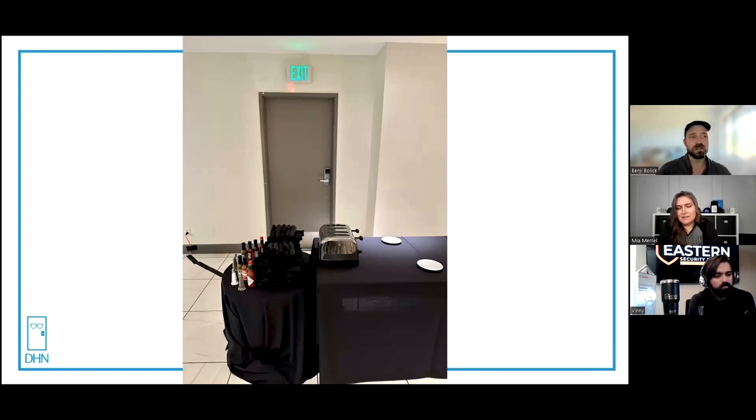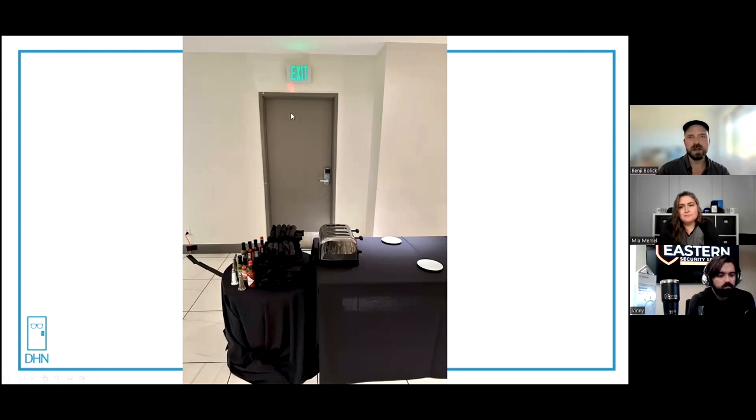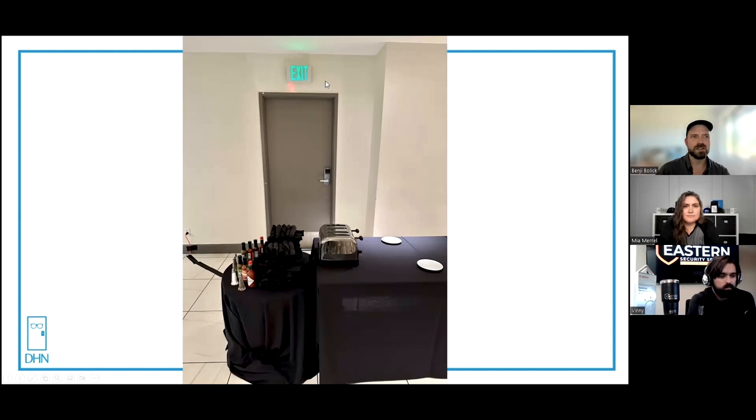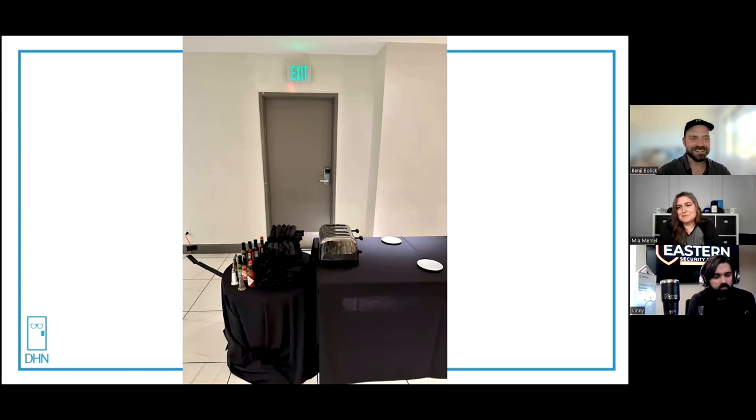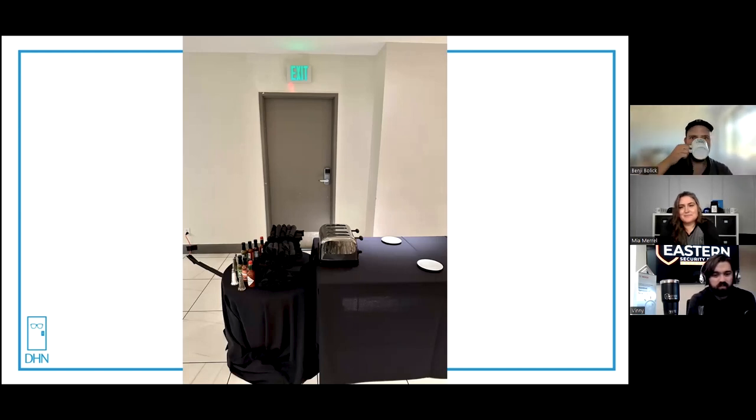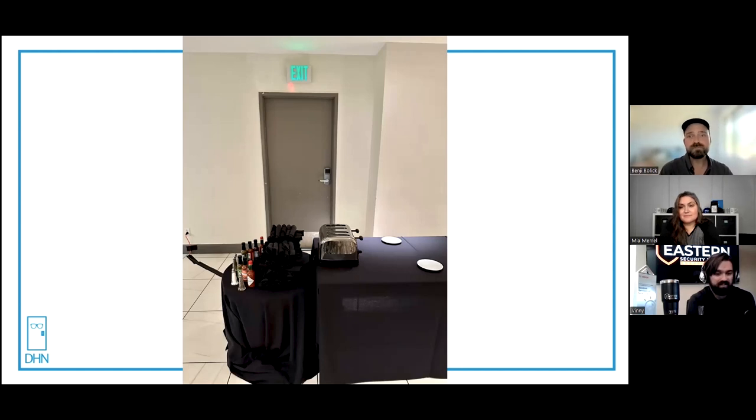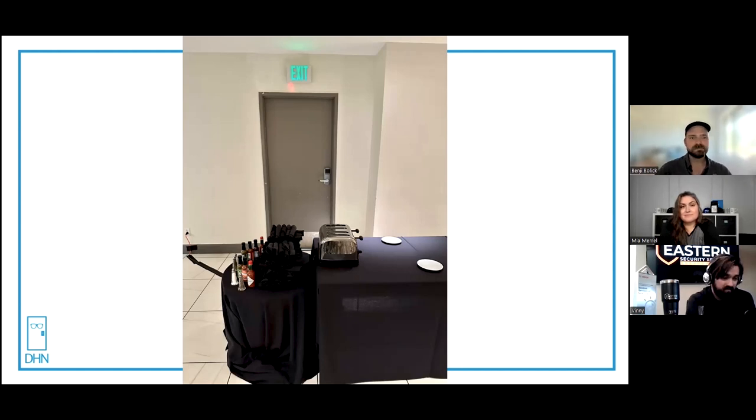That's true. Yeah, no, that's a newer version of the sign. I mean the door has seen some wear and tear, so the door's probably original with the building, but yeah they probably redid something up there and like, oh let's continue to have this exit sign up there. And not that it would even excuse it, but I mean there's nothing even there directing someone to you know an actual egress door for them. So there's just nothing, they're going to get there and the door is going to be locked.